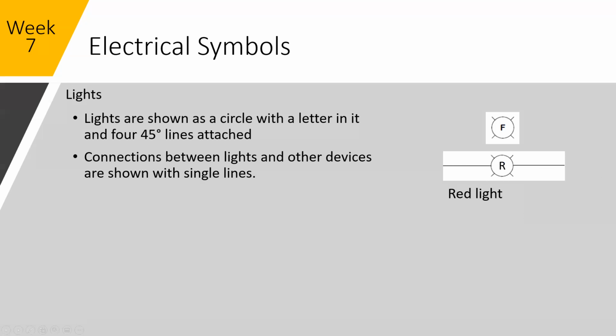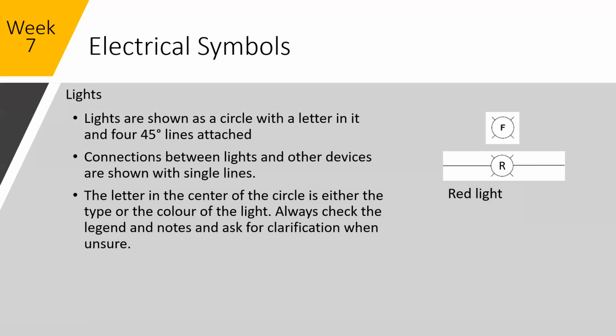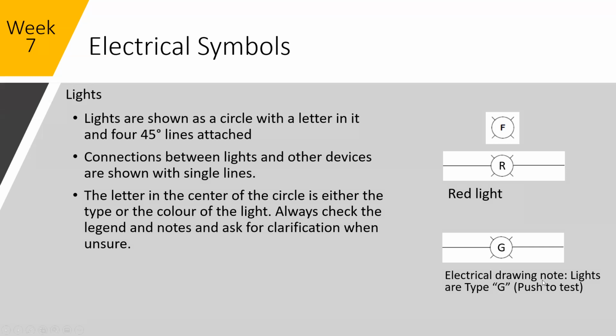R here stands for red light. F here could stand for fault. The letter in the center is either the type or the color of the light. Again, check the legend or check notes in the drawings. Off to the right of the drawing, typically there'll be a description as to what's going on. G here could denote, again, notes. Electrical drawing note: lights are type G, push to test. Type G, who knows what that means? There's probably going to be a list or another note elsewhere that says what type G are.